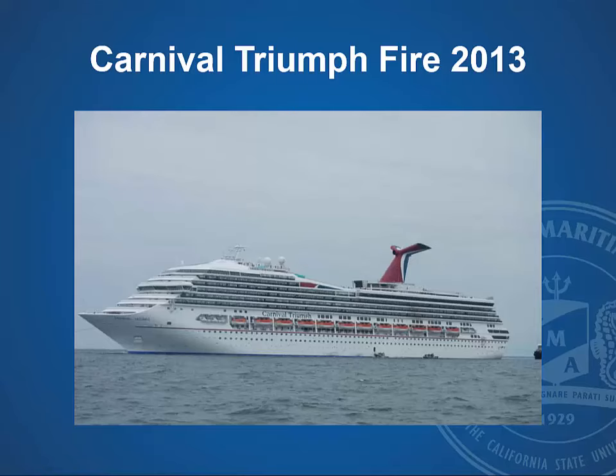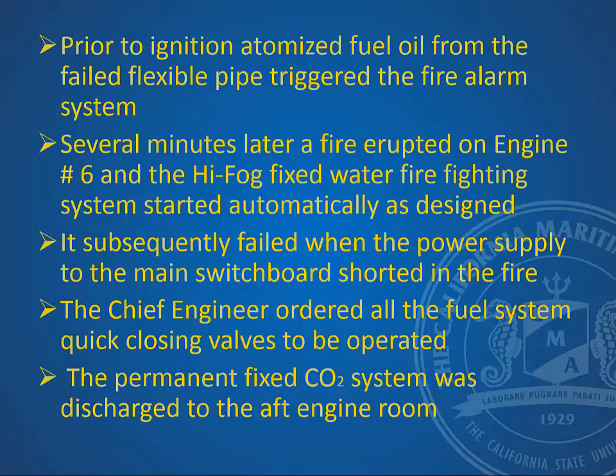Now, these generators were not damaged themselves. The fire melted down the cable that disconnected these generators from the main switchboard. Number 4 SSDG was undamaged, but it was out of service and opened up for an overhaul period. Prior to ignition, atomized fuel oil from the flexible pipe triggered the fire alarm system. So they got an alarm, and they were responding to the alarm. Several minutes later, a fire erupted in engine number 6, and the Hi-Fog fixed water firefighting system automatically started, as it was designed to do.